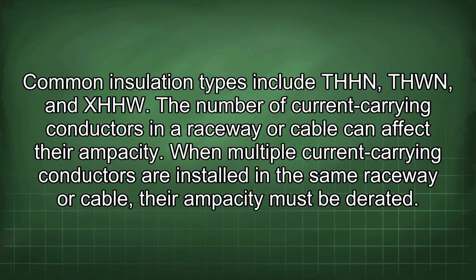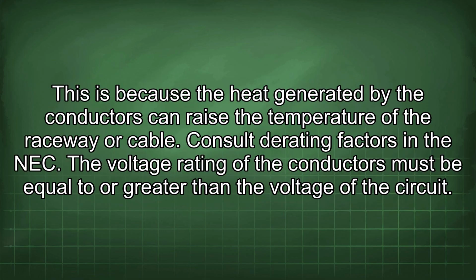The number of current-carrying conductors in a raceway or cable can affect their ampacity. When multiple current-carrying conductors are installed in the same raceway or cable, their ampacity must be derated. This is because the heat generated by the conductors can raise the temperature of the raceway or cable. Consult derating factors in the NEC.